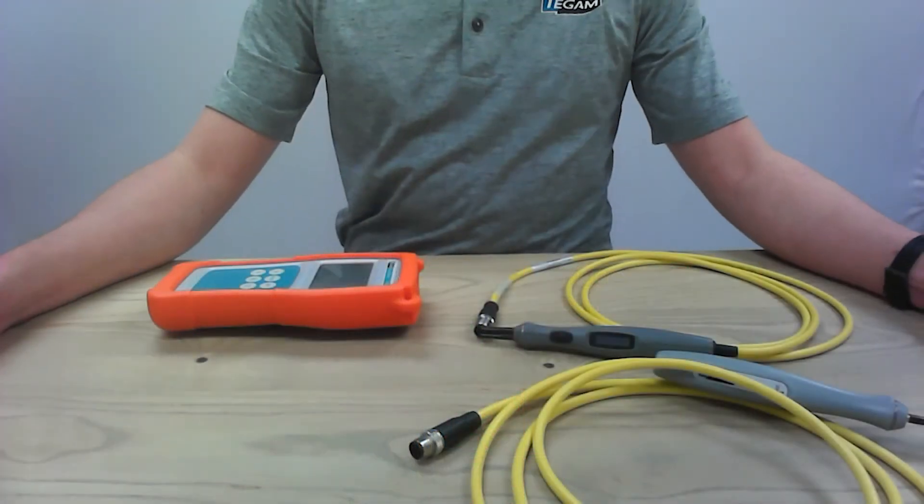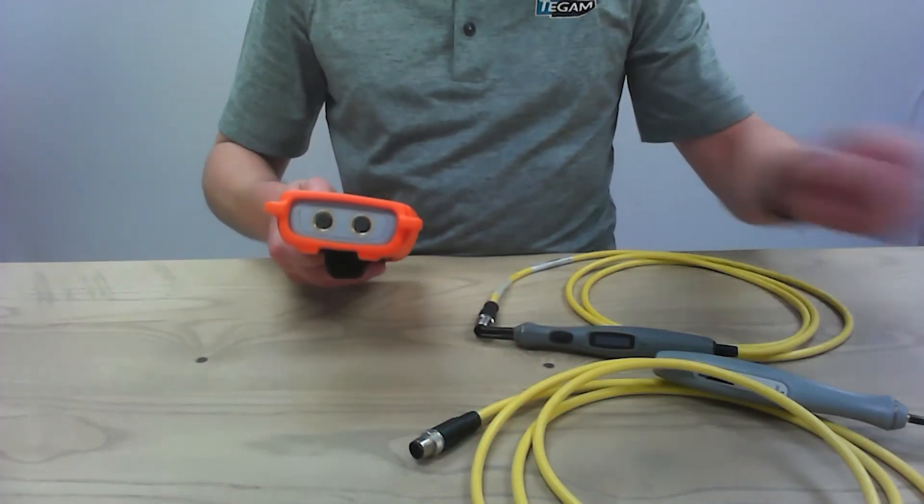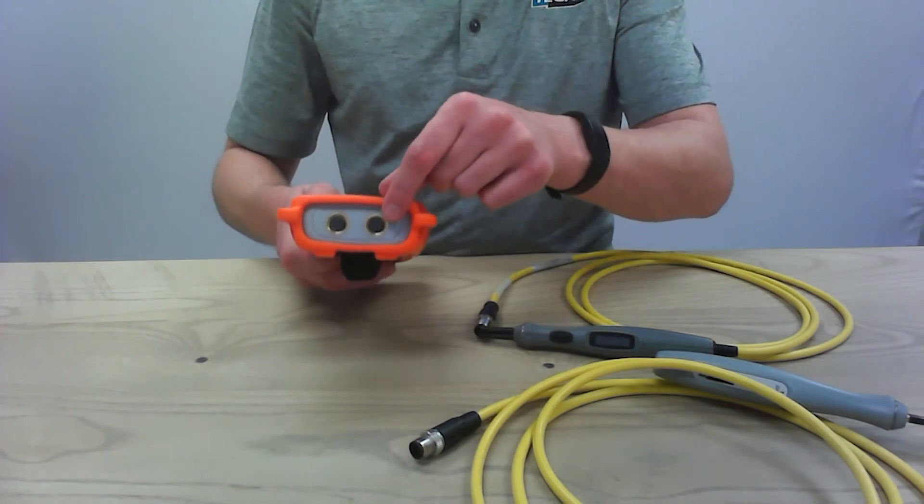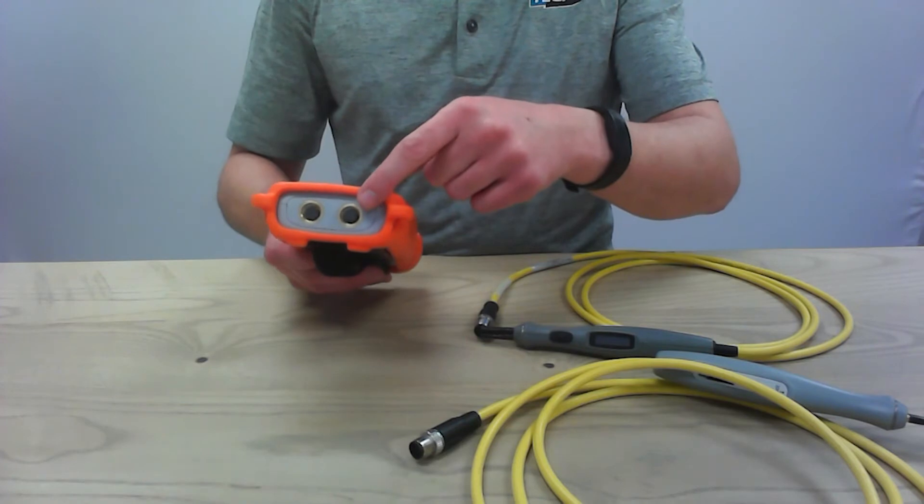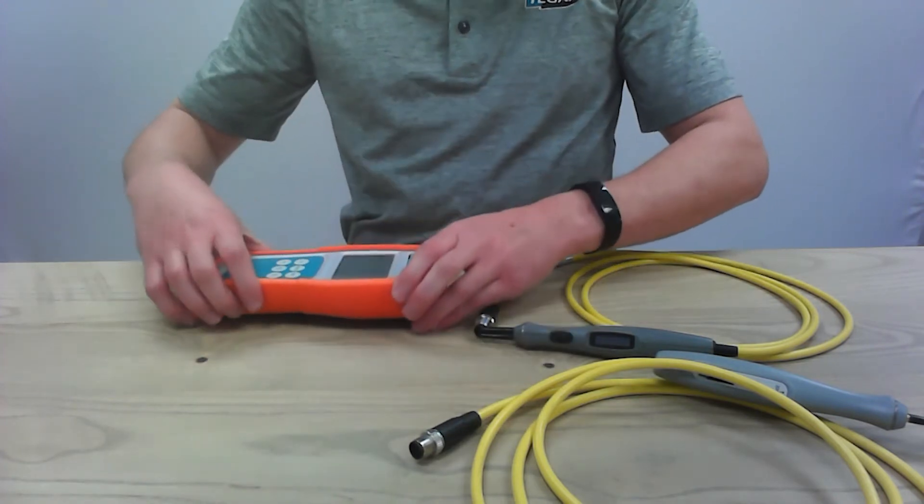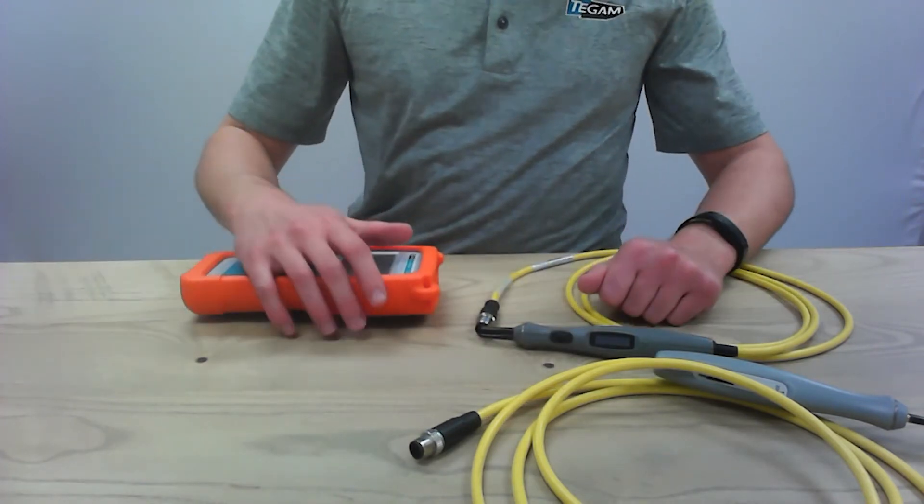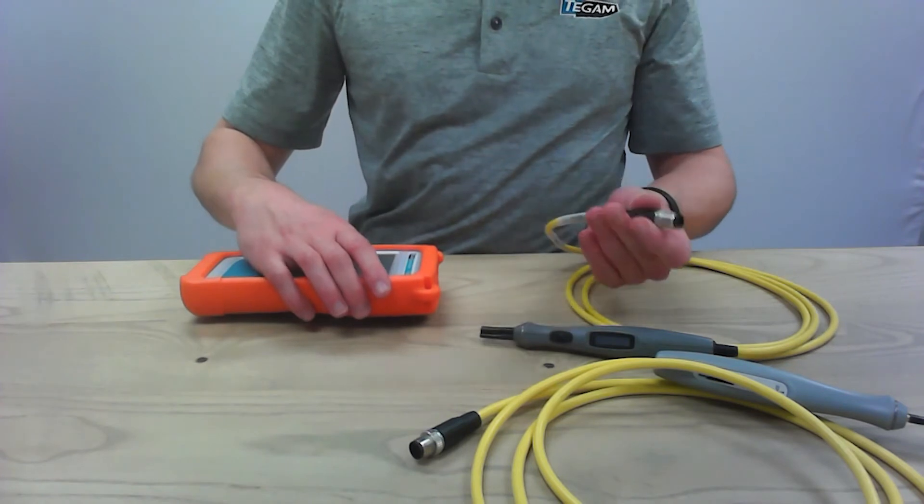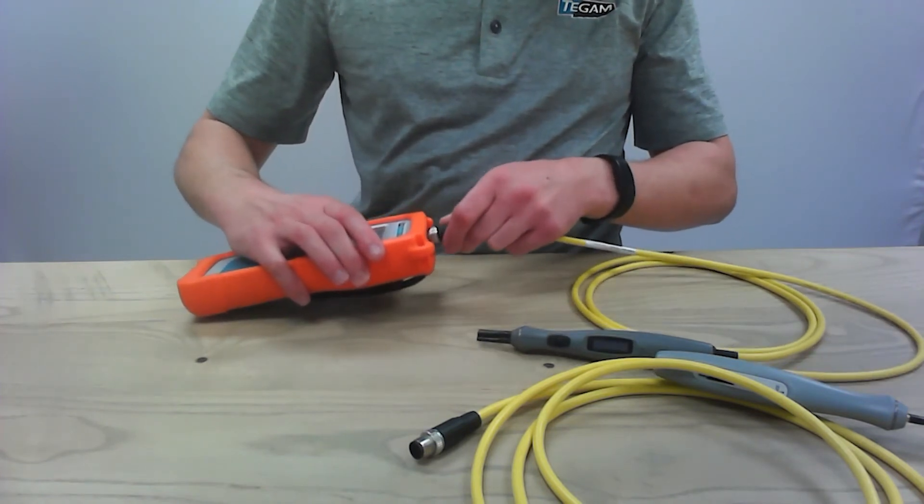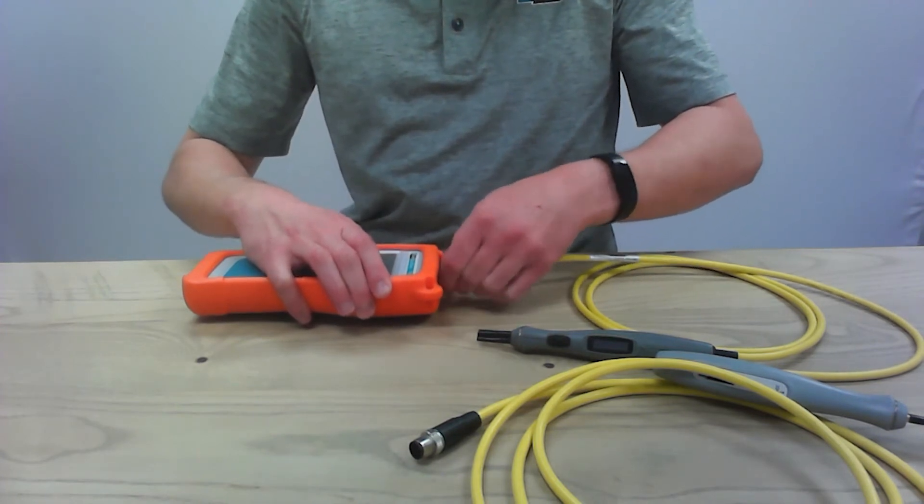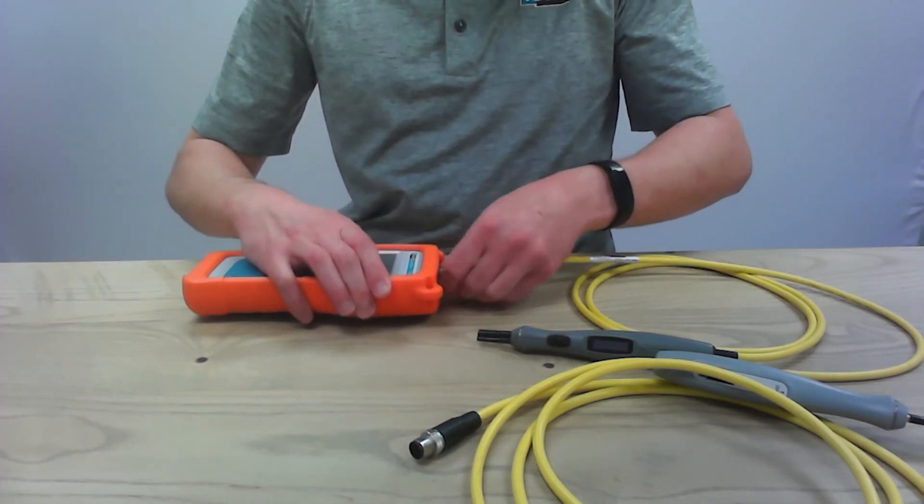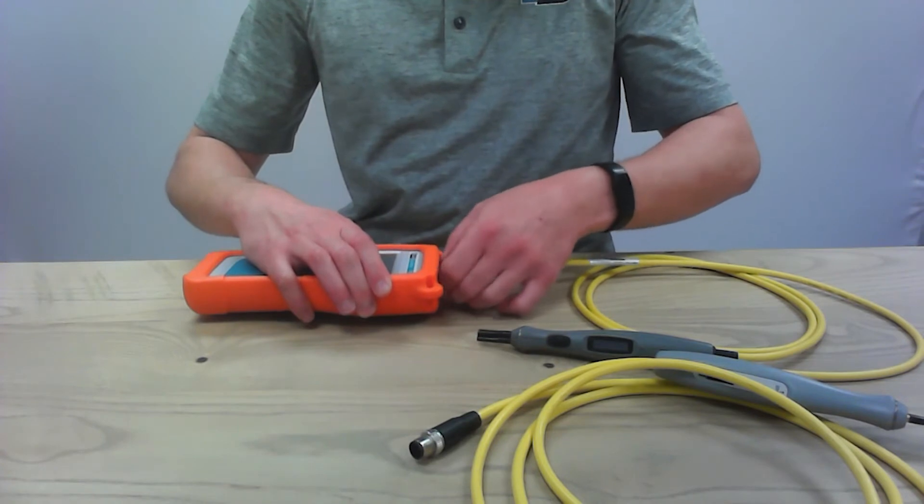To connect the display probe to the unit, first make sure that you're plugging it into channel one. Channel one is on the left-hand side when you're looking straight on from the unit. Turn the unit off if it's not already, and then take the display probe connector, line it up with the tab, push, and then screw the threaded leads into the connection.